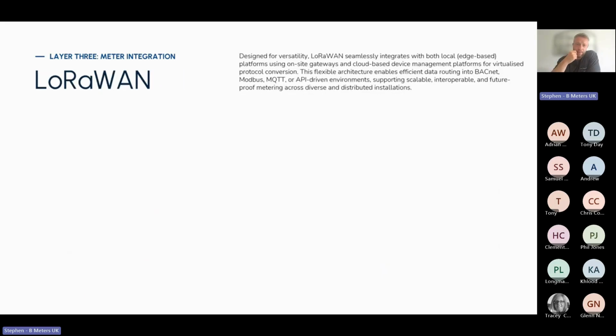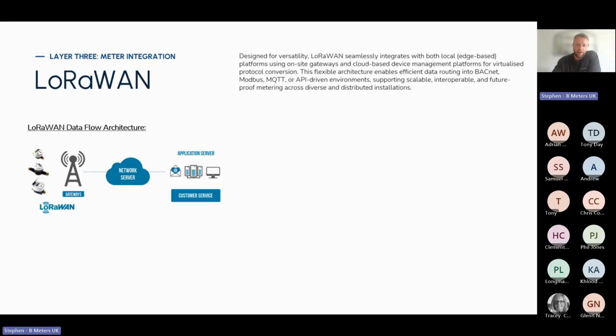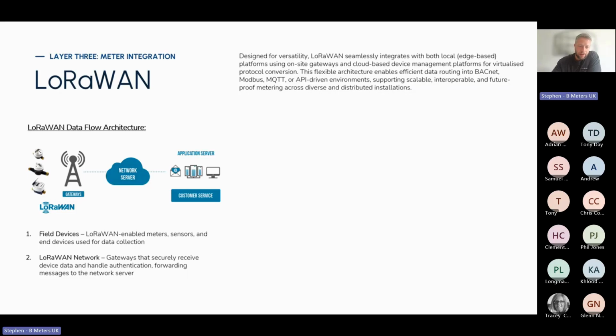Now, LoRaWAN is designed for versatility. LoRaWAN seamlessly integrates with both local platforms using on-site gateways and cloud-based device management platforms for virtualized protocol conversion. This flexible architecture enables efficient data routing into BACnet, Modbus, MQTT, and API-driven environments. So typical LoRaWAN data flow architecture is devices, gateways, network server, application server, and then the customer service. So field devices: LoRaWAN enabled meters, sensors, and devices for data collection. LoRaWAN network gateways securely receive device data and handle authentication, forwarding messages to the network server and device management platforms. Now these can be both local and cloud-based platforms.